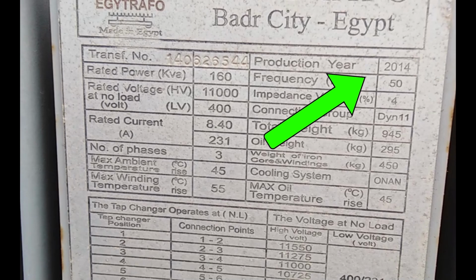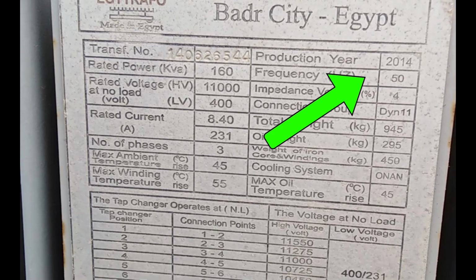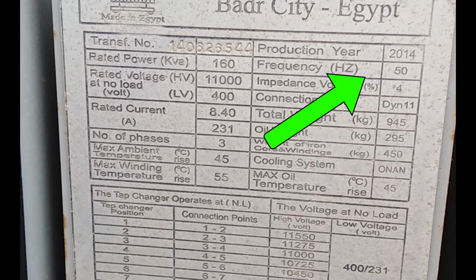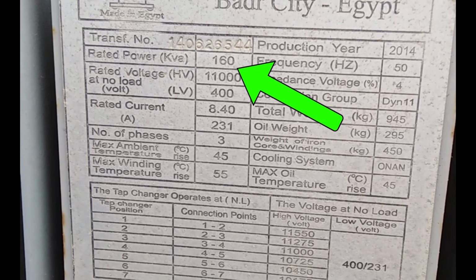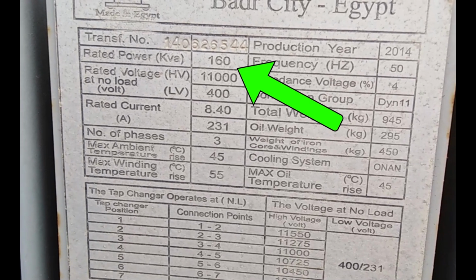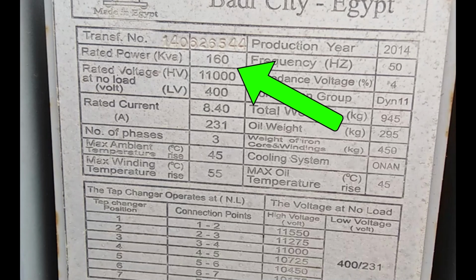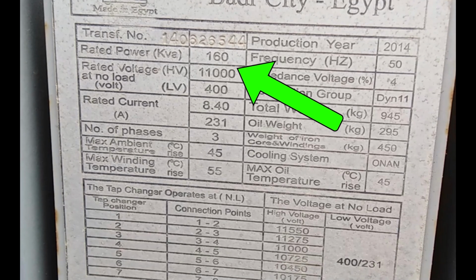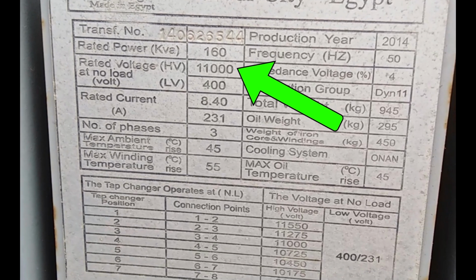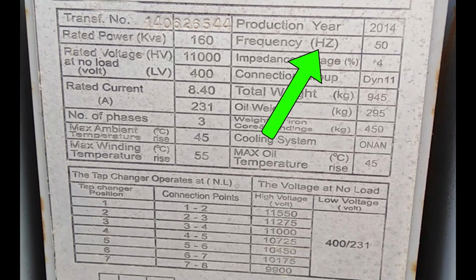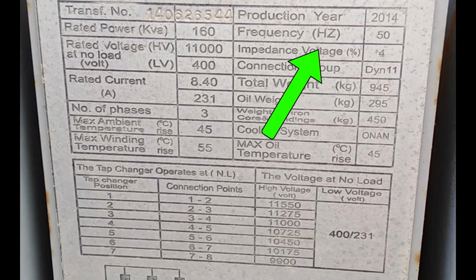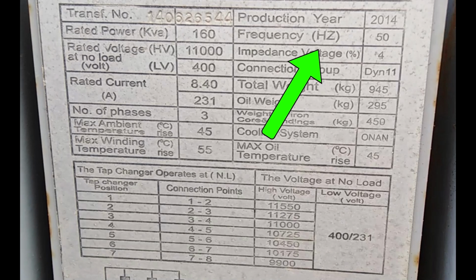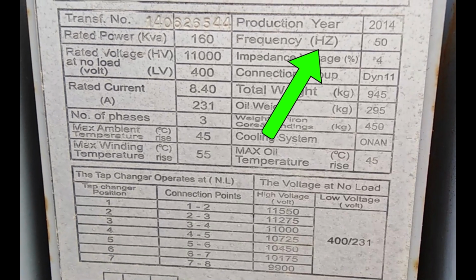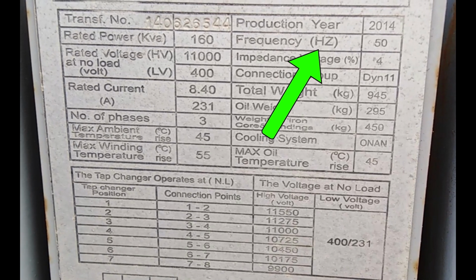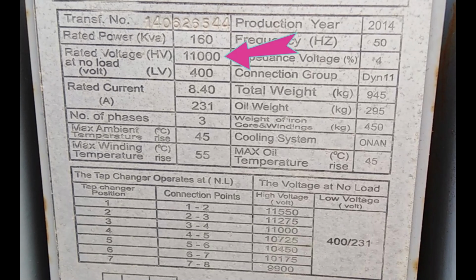This date is essential for knowing the age of the transformer and planning its life cycle, including maintenance schedules. Then, there's the power rating, coming in at 160 kVA for this beast. This tells us the maximum amount of power it can handle, which is crucial for ensuring it meets the demands of the system it's powering. Frequency is up next, listed at 50 Hz. This matches the power grid frequency in many parts of the world, indicating our transformer is designed to operate in those regions. Now, let's talk about voltage.